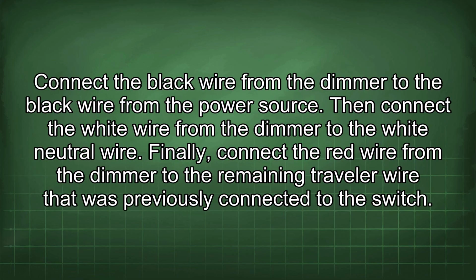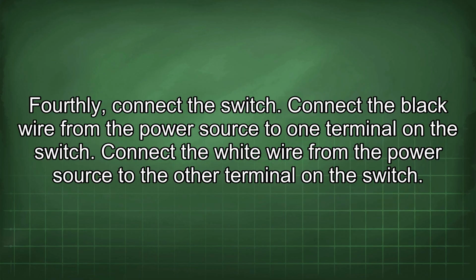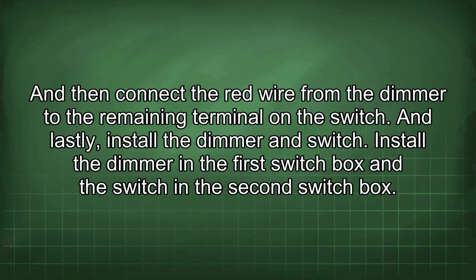Connect the black wire from the dimmer to the black wire from the power source. Then connect the white wire from the dimmer to the white neutral wire. Finally, connect the red wire from the dimmer to the remaining traveler wire that was previously connected to the switch. Fourthly, connect the switch. Connect the black wire from the power source to one terminal on the switch. Connect the white wire from the power source to the other terminal on the switch. And then connect the red wire from the dimmer to the remaining terminal on the switch.